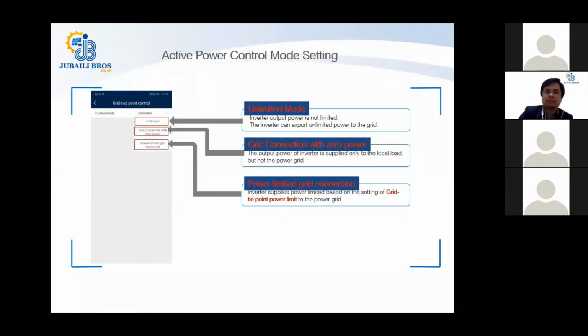The power control modes under the grid tie point are the unlimited mode, grid connection with zero power, and power limited grid connection. Just to give you a basic understanding, this type of control looks at the power being fed at the grid tie point. So what is the grid tie point? The grid tie point in your PV system is an AC combiner or LV panel of your house or your facility, where the power from the grid and from your PV system comes and accumulates. Either it goes towards the load, or it goes towards the grid. That point is the grid tie point, or POC, which is the power point of connection in your PV system. In that scenario, you will be using a power meter to constantly read the direction of flow of power and the amount of power being fed in each direction to do the control.